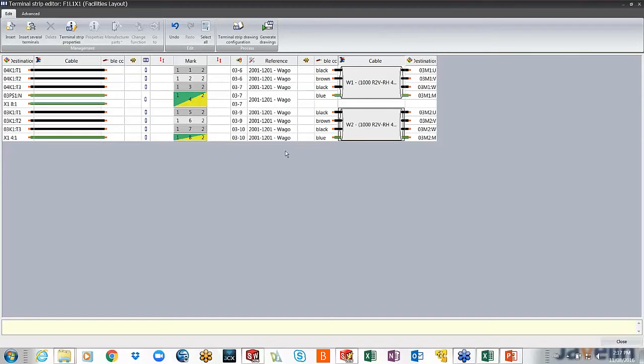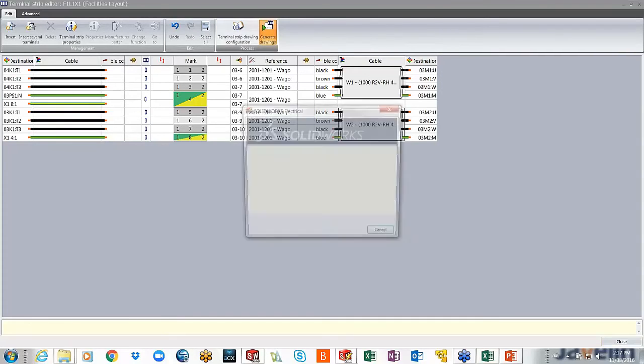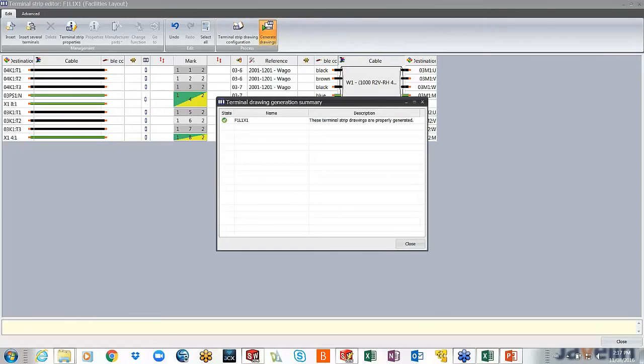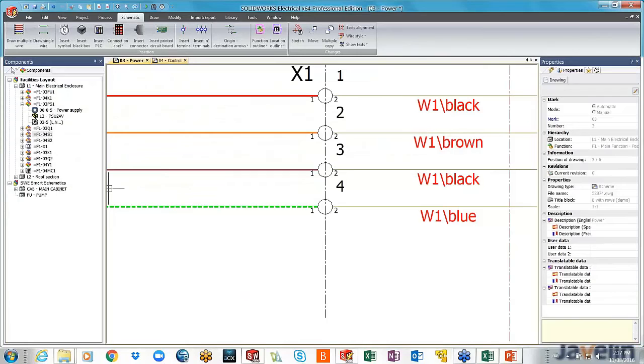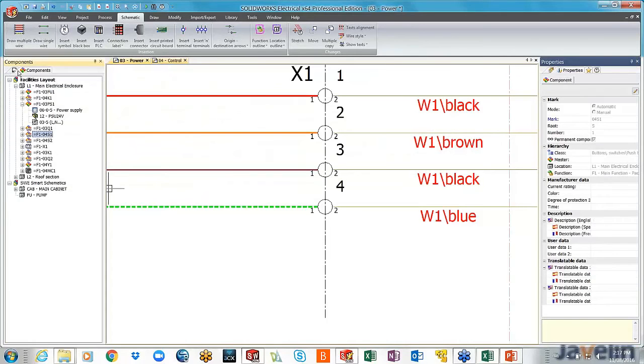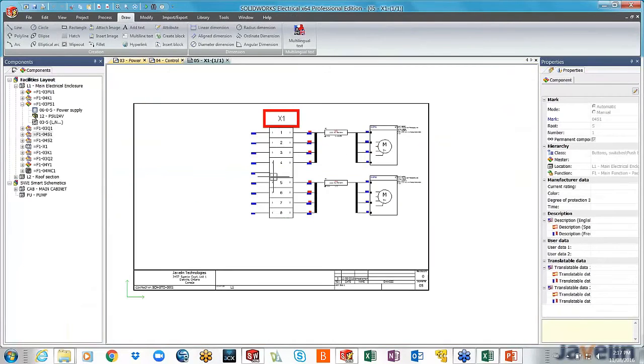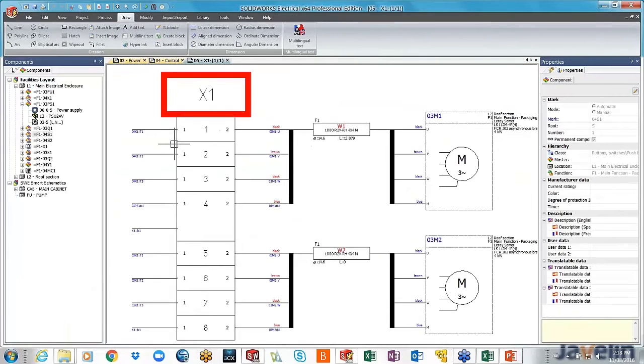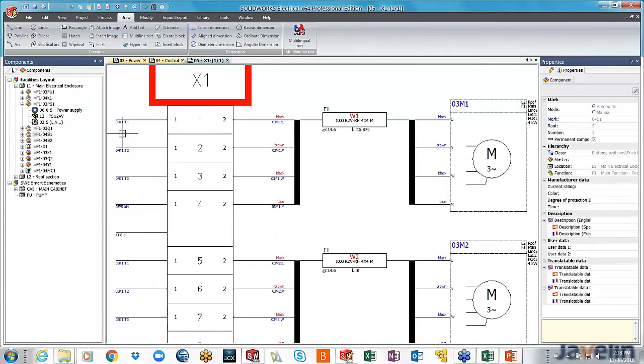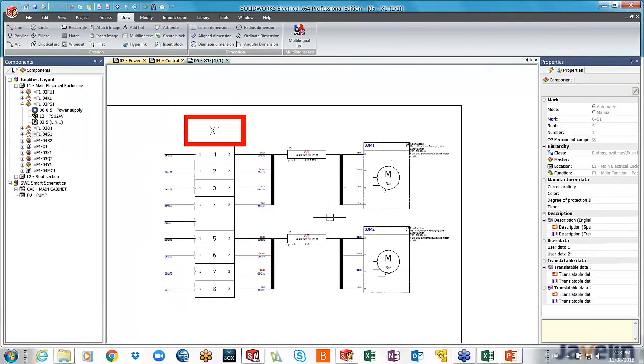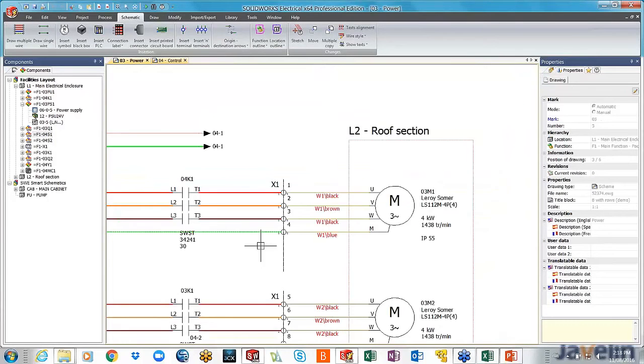Now I have been at a point where you're rushing through your project, you don't have time to explain everything you've done. Your terminals are not done or you don't have a terminal layout. You kind of let the guy on the floor decide how things are going to be wired. However, in SOLIDWORKS Electrical, you can actually generate terminal strip drawings by simply clicking a button. No matter where you've placed your terminals through the drawing, it will generate a terminal strip drawing for you. It captures the right information you require. It tells you what's going in, what's going out, what cables, what devices, and which pin numbers any of these objects are connected to.